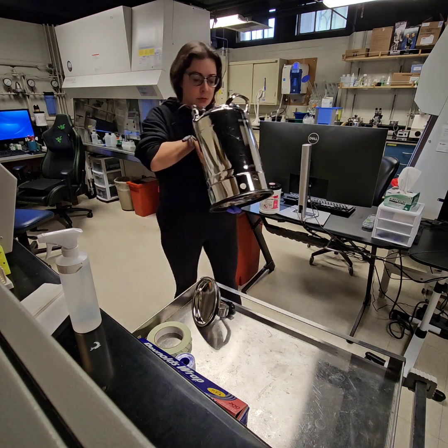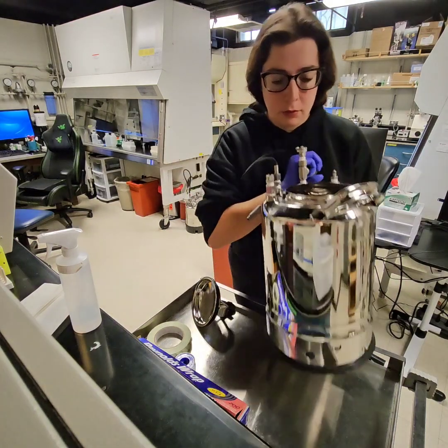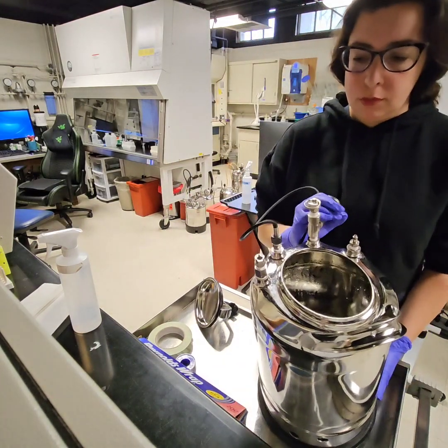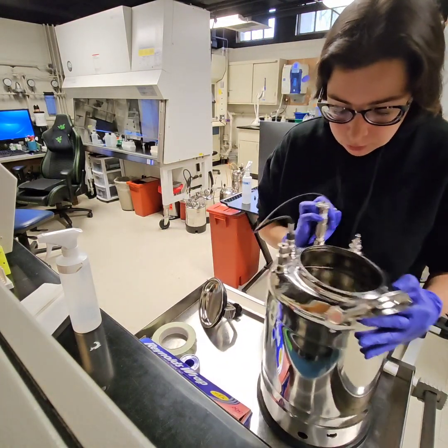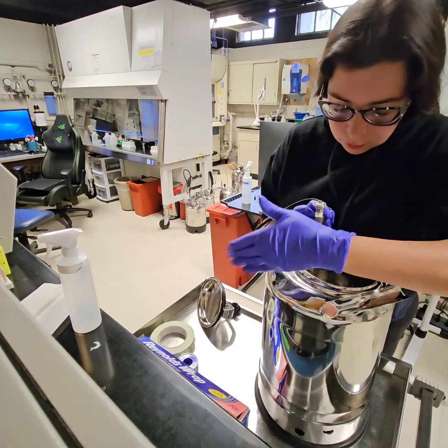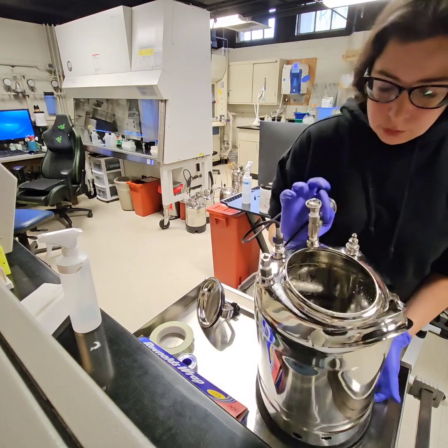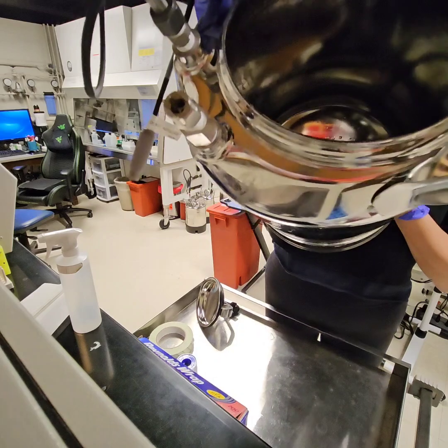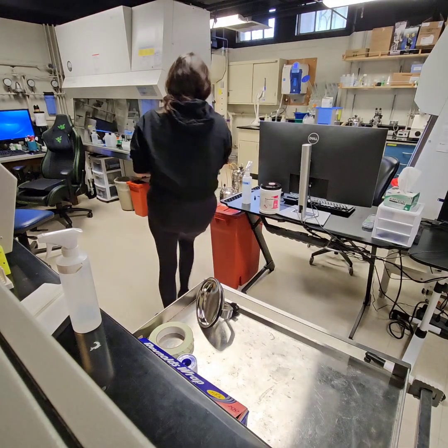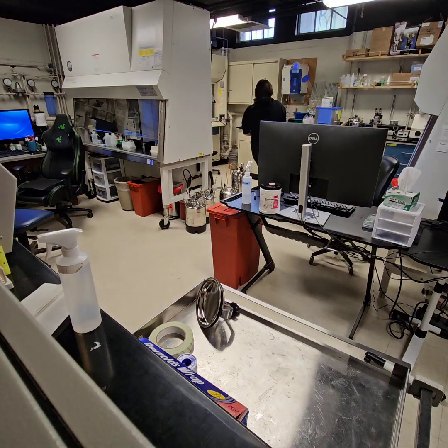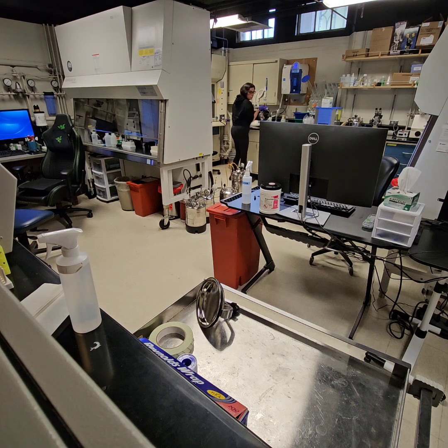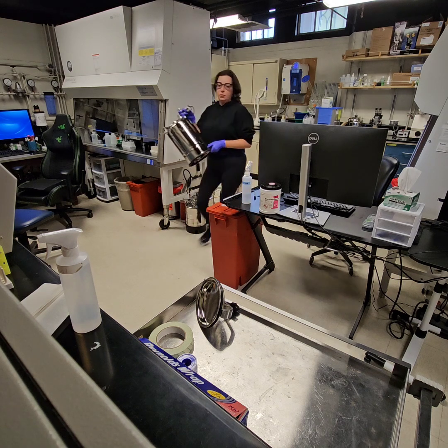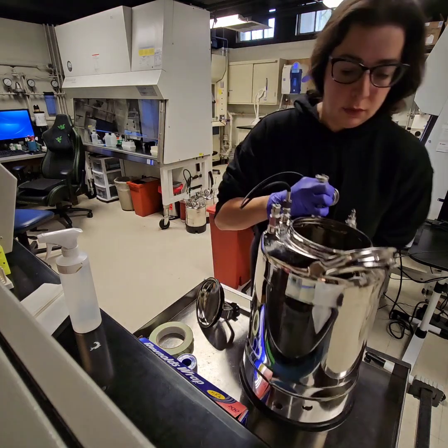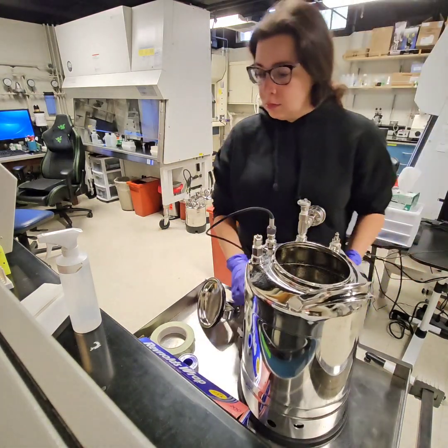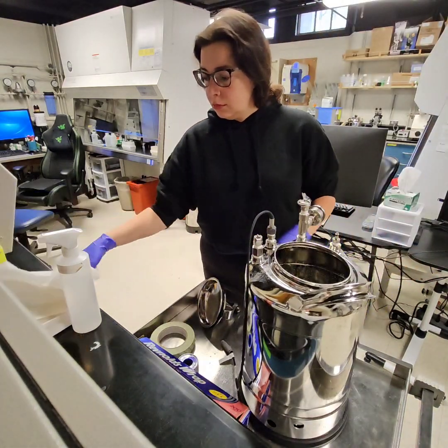So again, you want to do this in the hood because you don't know what type of mold, particles, things might be in the air. So you'll notice that I am now going to hit the sheath line that's in there because I want to make sure that anything that's stuck there falls down into the bottom so that I can empty it out, because if that goes into the autoclave, then it's going to stick to the bottom and crystallize. Sure, it'll be sterile crystals, but we don't want that.